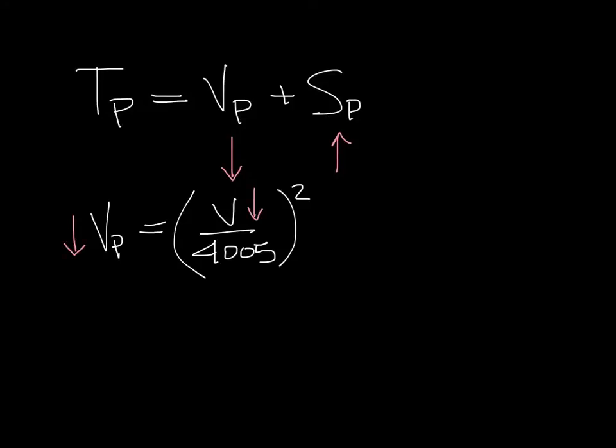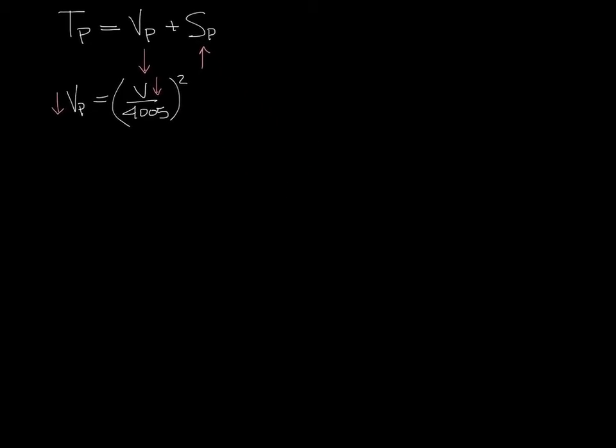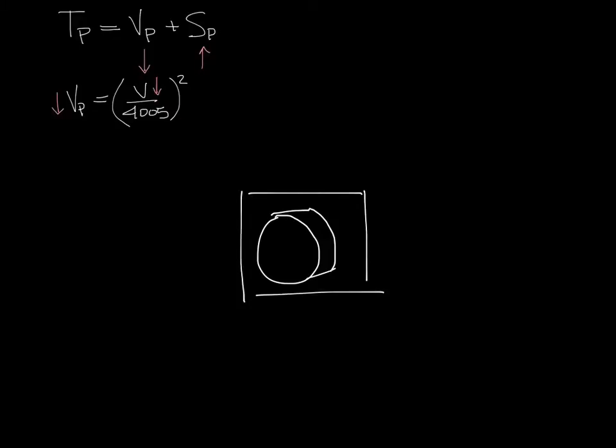To see how this works, let's look at a VAV box. A single duct box takes advantage of static regain by having a round inlet and a larger rectangular discharge. Let's move this out of the way a little, make a little room, and then let's draw a VAV box. So you have a round inlet on a rectangular casing.